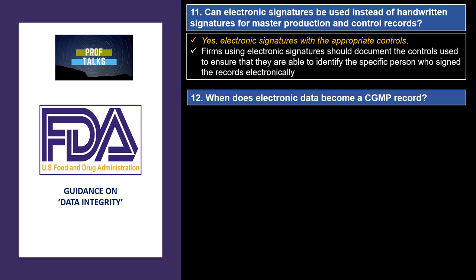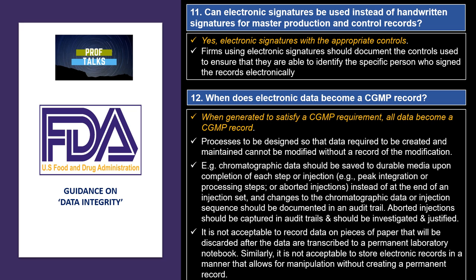When does electronic data become CGMP data? Whenever any data is generated to satisfy a CGMP record or a CGMP requirement, it becomes a CGMP record. Processes should be designed so that required data cannot be modified without a record of modification. For example, chromatographic data should be saved to a durable media upon completion of each specific step — such as integration or processing — not at the end of the entire process. Audit trail should be contemporaneous. Aborted injections should be captured in the audit trail, investigated, and justified. It is not acceptable to record data on pieces of paper first — the first entry should be made onto the original record itself.